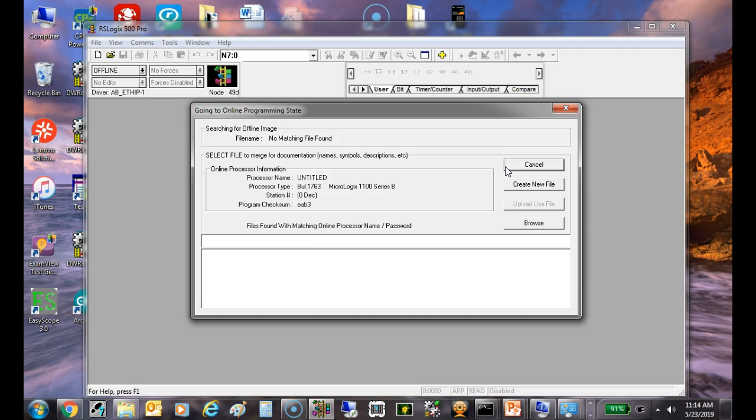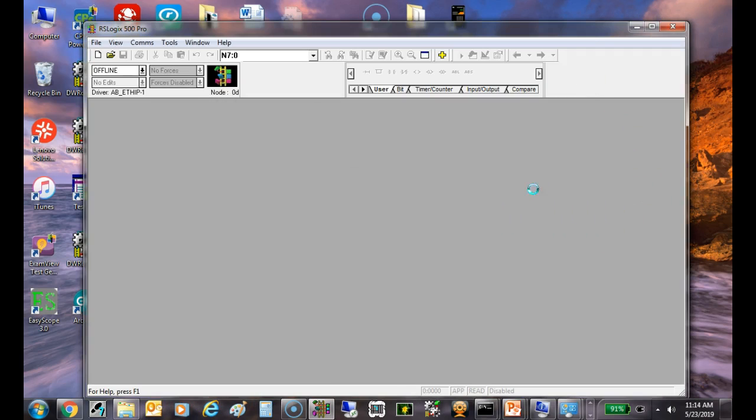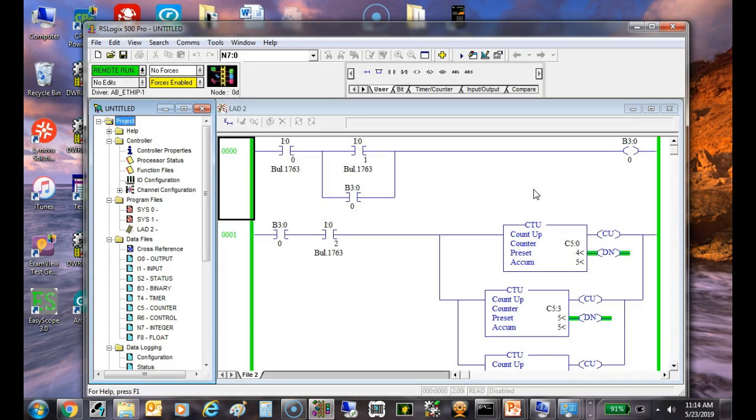I could select any IP, any PLC on the network and change programs, and we can create a new program. What did it do? It automatically uploaded whatever program happened to be in the PLC at the time. You lost all your symbols, so your symbols are not saved with your program when you compile it and send it over. One thing that they did with the TIA Portal is your symbols are saved. So if you upload a program, you get all your symbols. We don't call them symbols anymore. We call them tags, by the way.